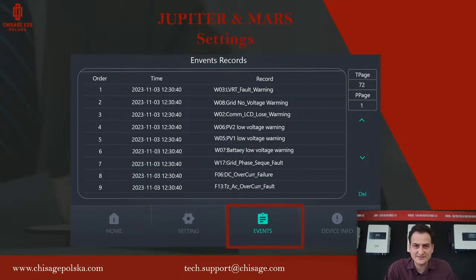That's about settings. Then we have the events. We have all the event records here, the history of events and current events. When an event is important, when any warning or fault is important, the alarm LED will show. So if the alarm LED is off, that means any of these warnings or faults are from history, or they do not affect the inverter working.